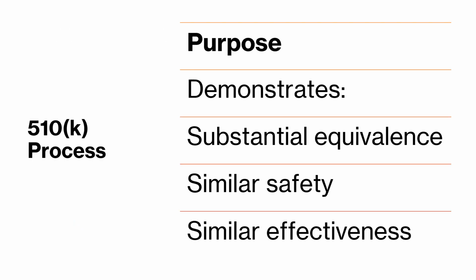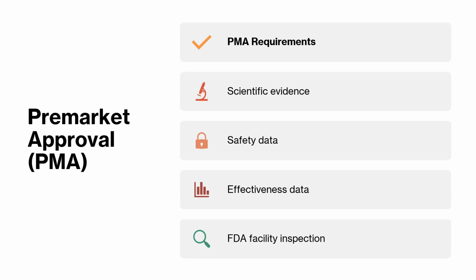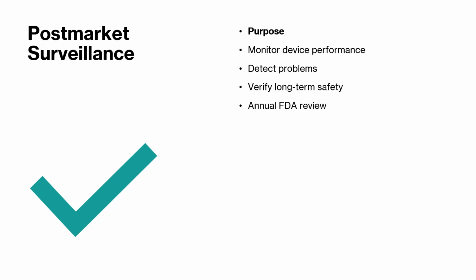A 510(k) submission demonstrates that a new medical device is substantially equivalent to a device already legally marketed in the healthcare industry. Pre-market approval, or PMA, is required for many Class 3 devices. Manufacturers must provide strong scientific evidence proving safety and effectiveness. After approval, some devices continue to be monitored through post-market surveillance programs. This helps identify potential issues and ensure devices continue performing safely.